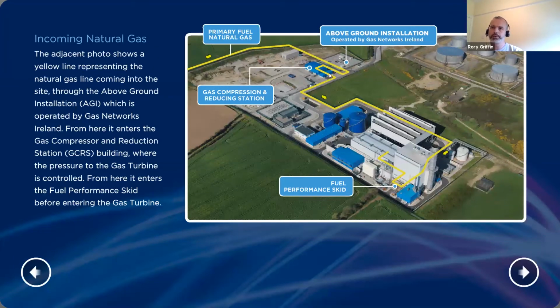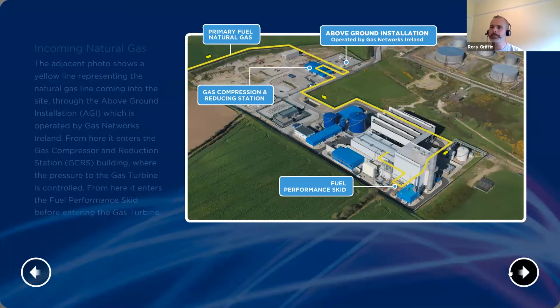Just, I suppose, one other thing to point out is that the gas coming in, which is metered, has a water content. As soon as that gas is put to the gas turbine, the water content is flashed off, so you have about 90% of the volume of gas that comes in. So you have the higher heating value here, and when you lose the water element, it's a hydrocarbon, you have the lower heating value actually being used in the gas turbine. Just in case you come across those terms, that's a small bit of context there.